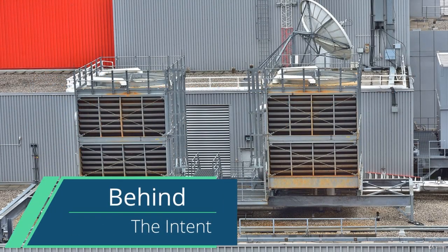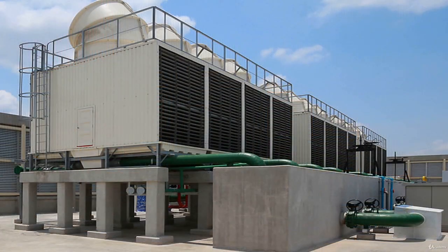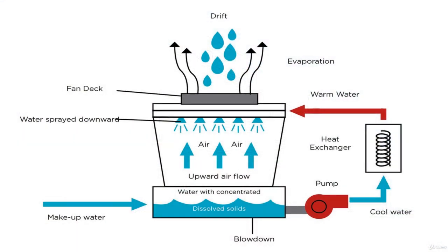Refrigeration systems remove heat, usually from air, to cool interior building spaces. This heat is expelled into either the atmosphere or another medium. A cooling tower or evaporative condenser removes heat in part by evaporating water. As the water absorbs heat, it changes from a liquid to a vapor. As the water evaporates, however, dissolved solids become more concentrated in the remaining water and eventually begin to deposit scale on the cooling tower or evaporative condenser elements, making such systems less efficient.